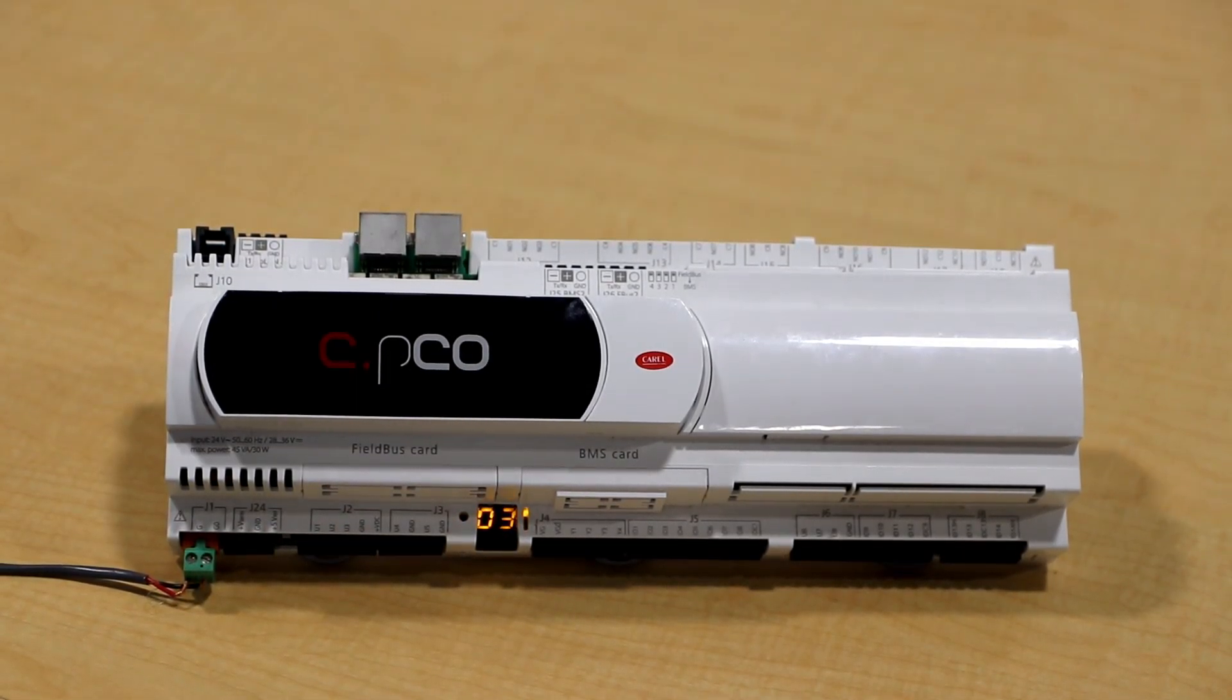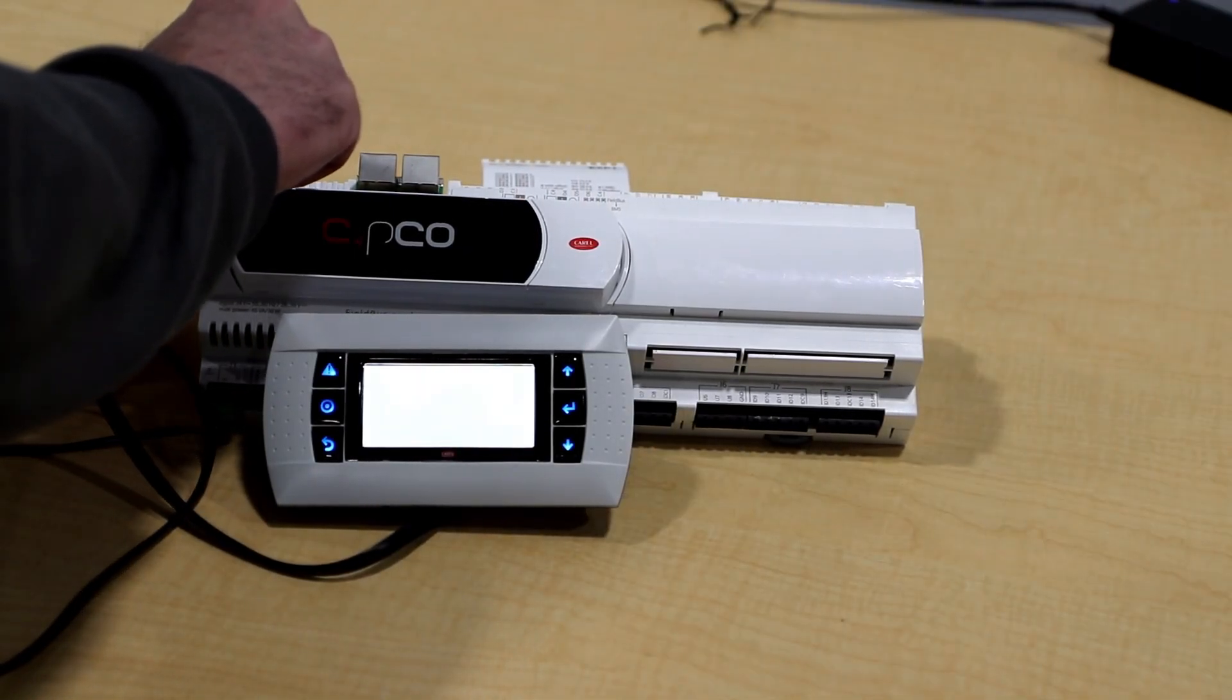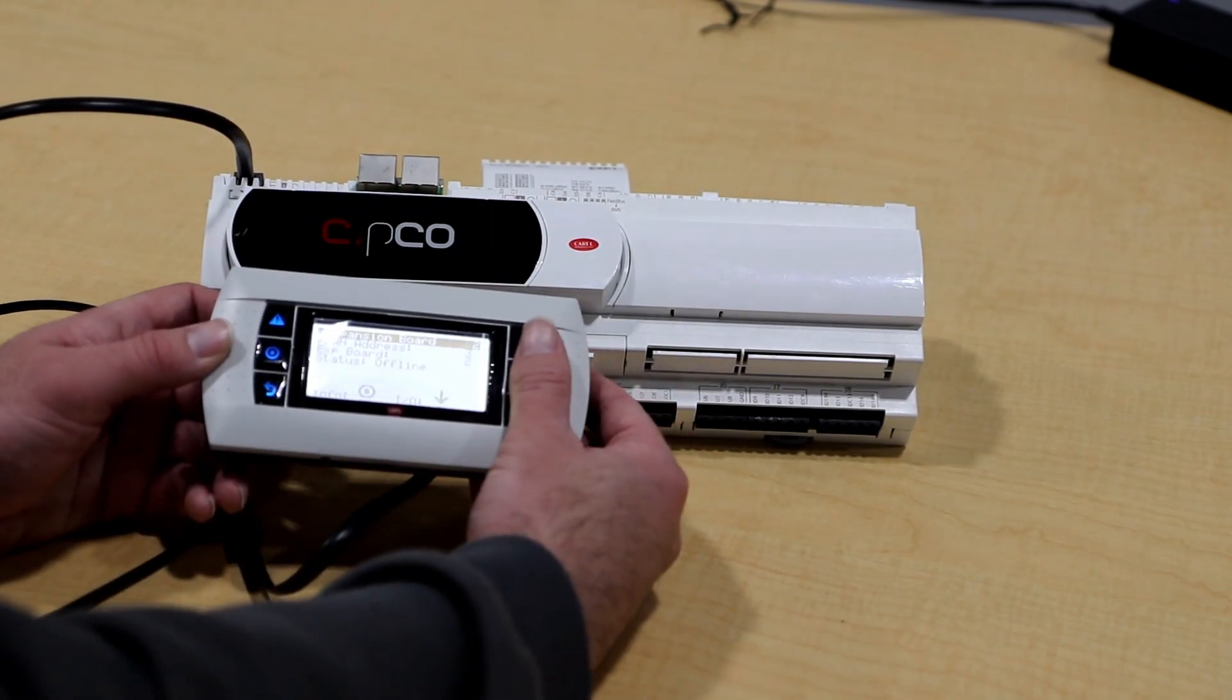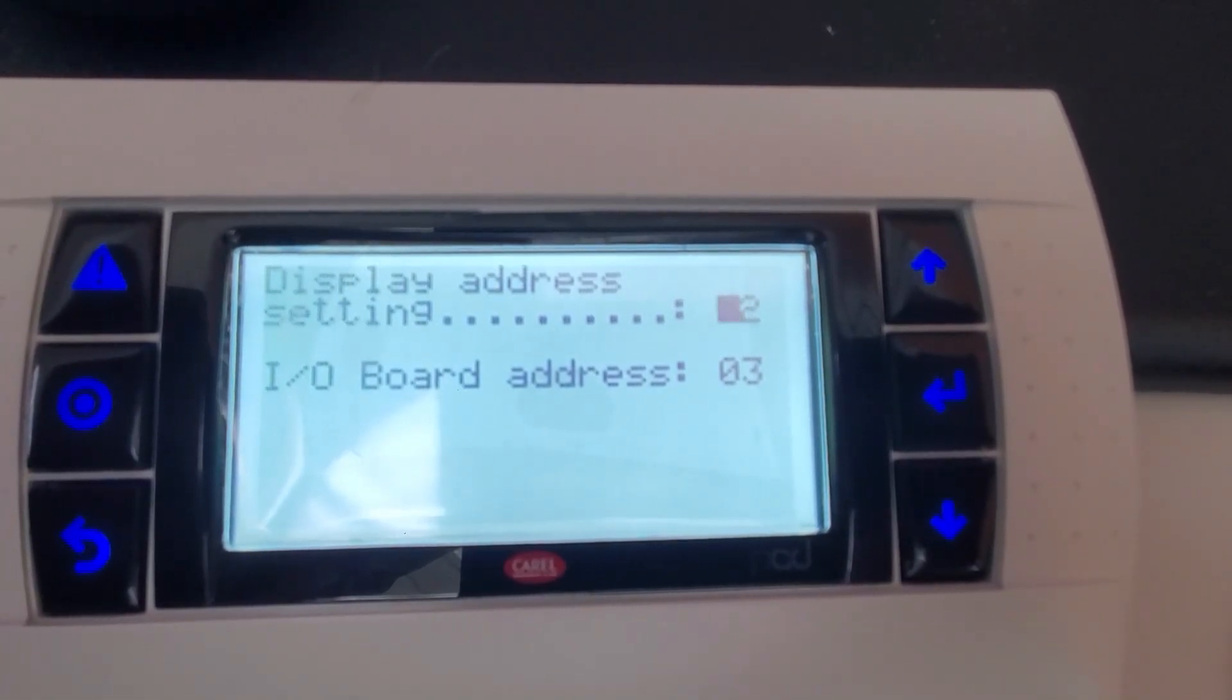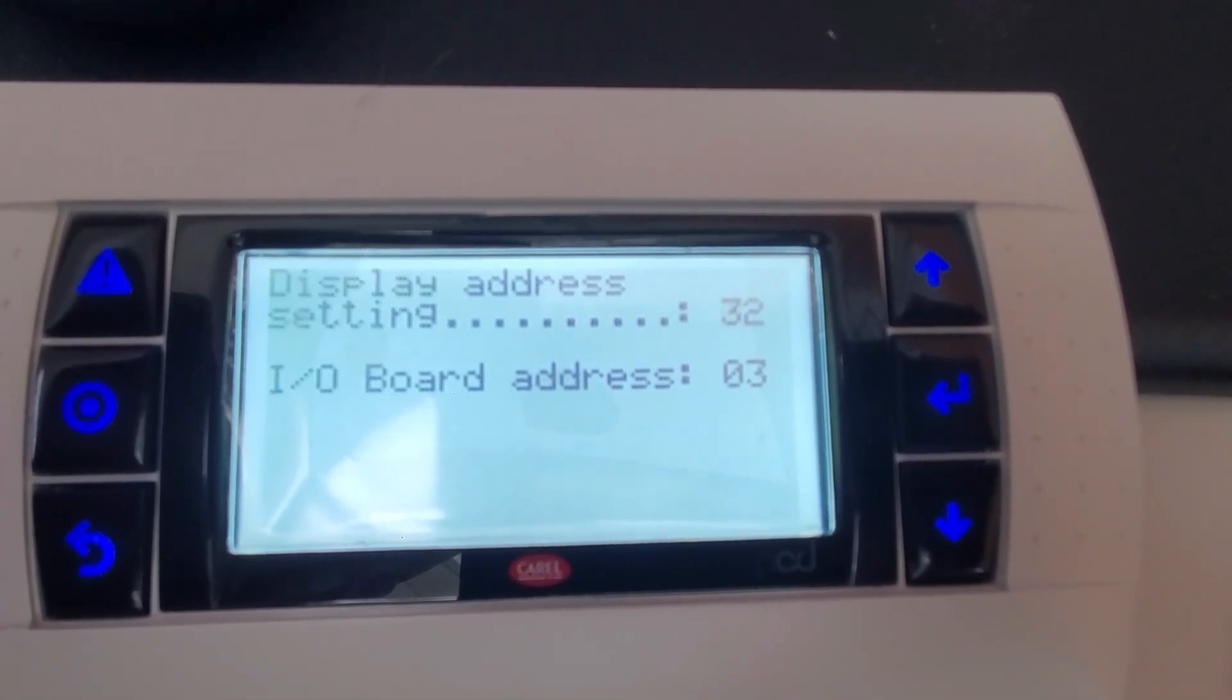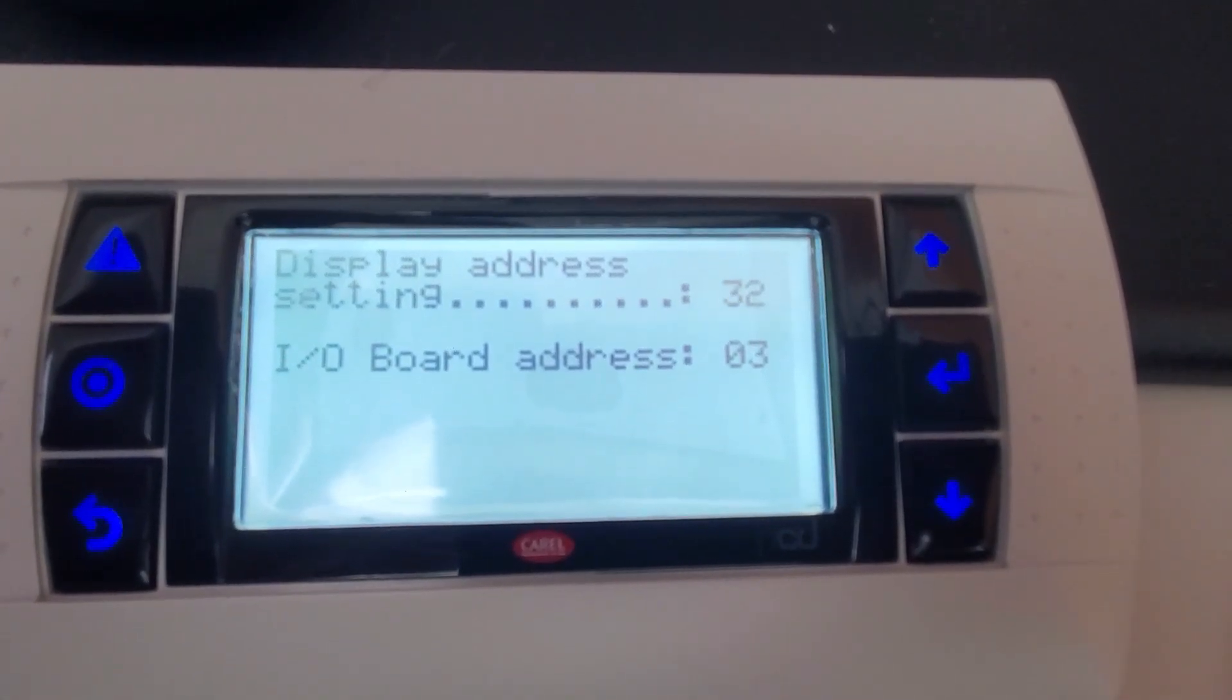This address can also be verified using the Carel display. Plug in the display and hold down the three buttons on the right side. This will pull up an addressing menu. The display address settings should be defaulted to 32. This is the address needed to sync the display with the controller. The IO board address should match the number on the controller's LED screen.